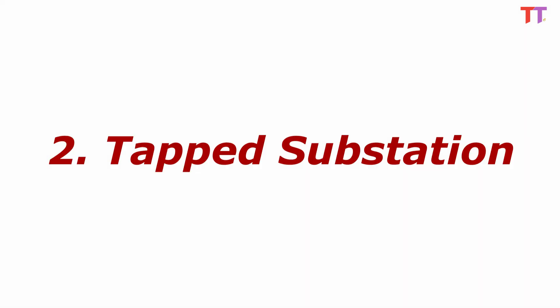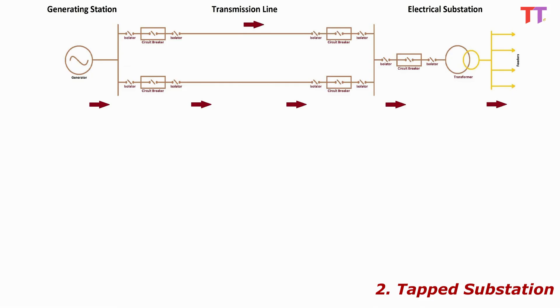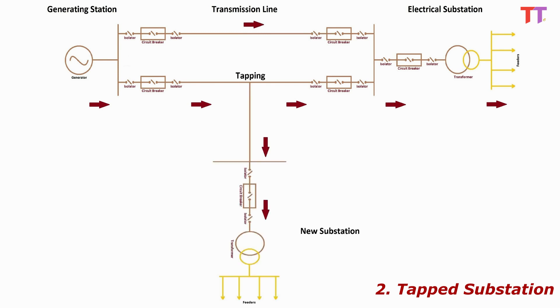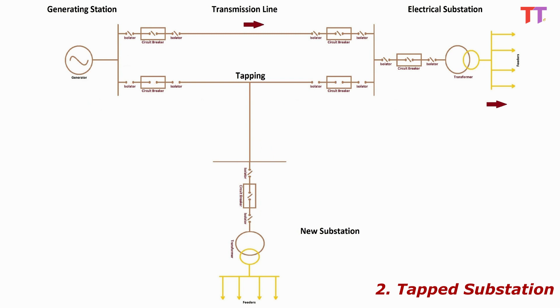2. Tapped substation. In this type of layout, on an existing nearby power transmission line, the power source for a newly constructed substation is tapped — hence called a tapped substation. This is also an economical supply system. However, in the event of source failure or in case of fault on the tapped source line, the complete substation goes dark, subsequently causing complete power breakdown of the connected load, same as in the case of a radial substation.